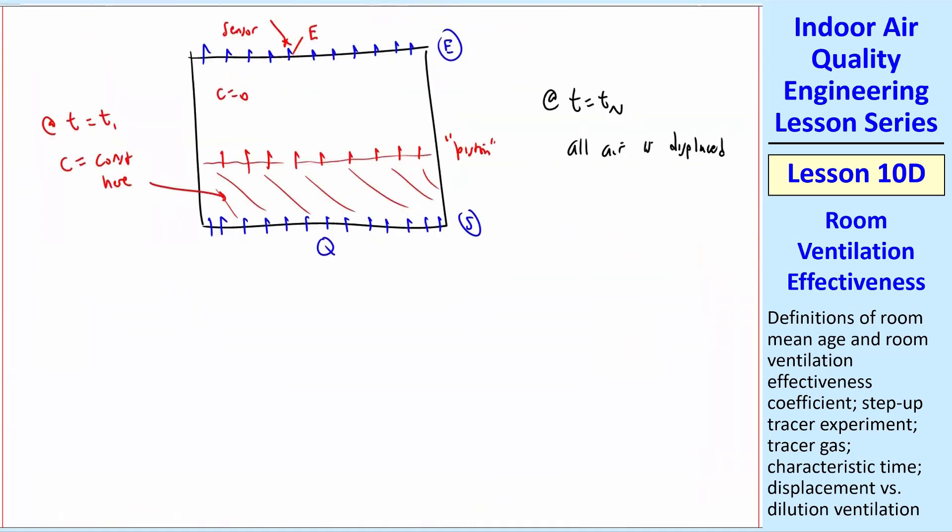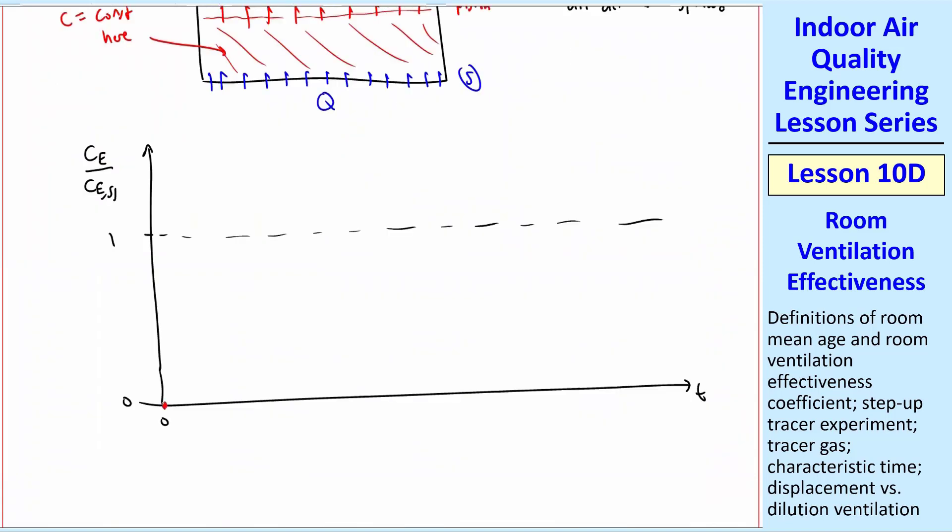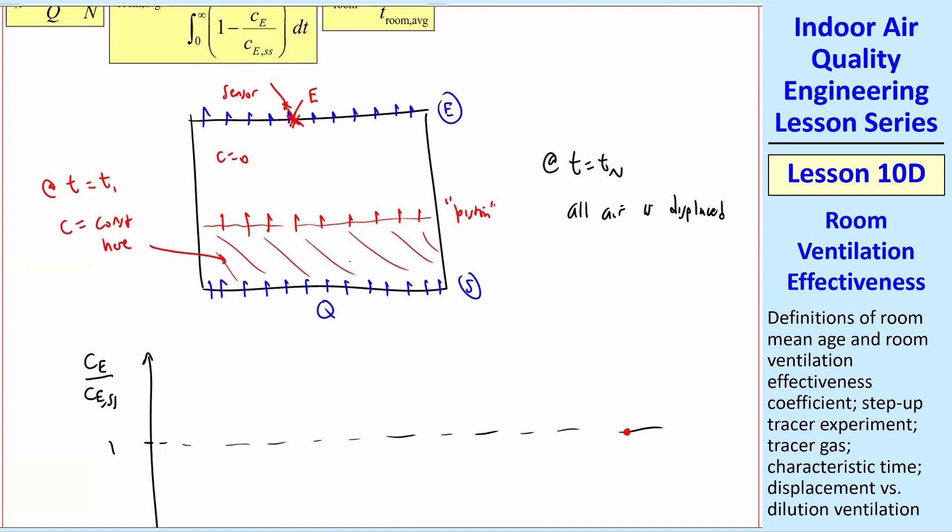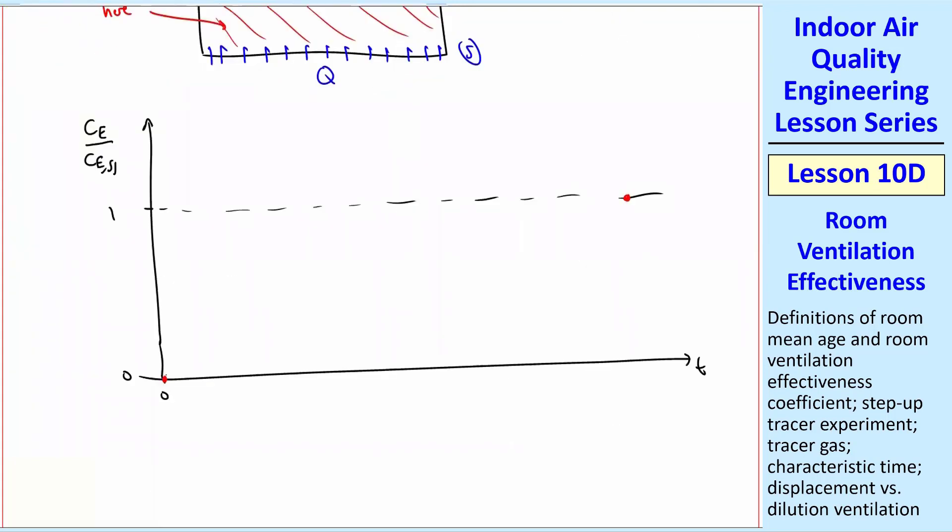So it takes time TN for this air to move all the way up to be exhausted. What does this look like in terms of our plot? We know we're going to start at 0. Suppose you're sitting at this sensor. How long does it take for this to sense anything? It's going to sense C equals 0 until this piston, this interface, reaches the top. That's going to take time TN. So we can easily plot this. C is 0 until we reach this magic time TN. And then suddenly it'll be a step function. Just jump right up to 1 and then be 1 from then on to infinity if you keep injecting that contaminant into the room.